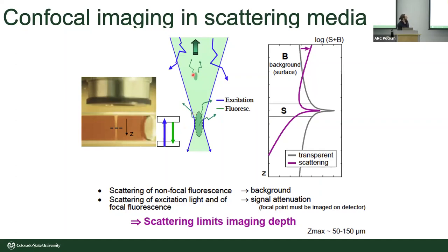To make matters worse, we can have fluorescence photons that are generated and emitted back in this region of the tissue scatter and actually make it through our detection pinhole. And that registers as a background signal that then corrupts what little image we did get in the first place. So I'm sort of using confocal as a straw man here, but it is true that we're very limited because of all of these different effects. And without being too specific about illumination wavelengths or the sample, you can think about 50 to 150 microns as a good rule of thumb for how deep confocal can go.